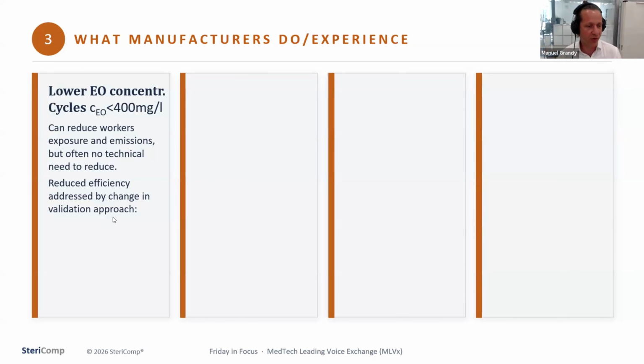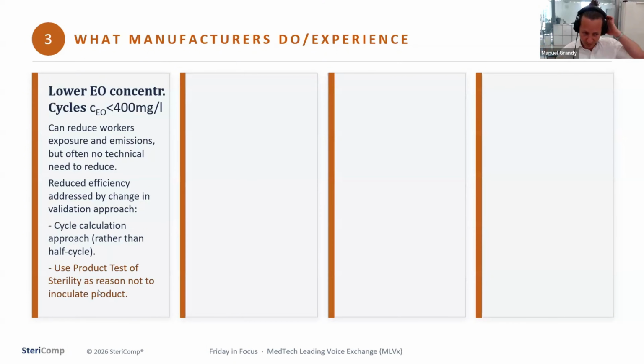So this reduced efficiency is mainly addressed by a change in the validation approach, moving to a high-level cycle calculation approach rather than a half-cycle approach, which I'll briefly discuss later. But then there's the use of product tests of sterility as a reason not to inoculate the product. This is the ugly one, unfortunately proposed by some companies, and it will put you in trouble. I'm going to present on this for a while and explain the consequences and why this is not a good idea.